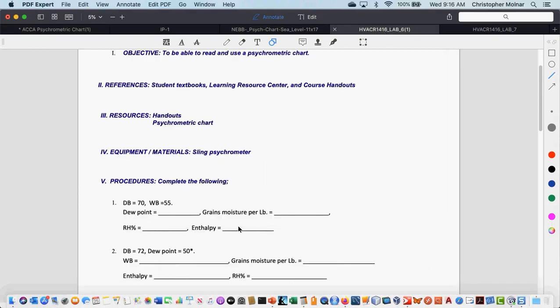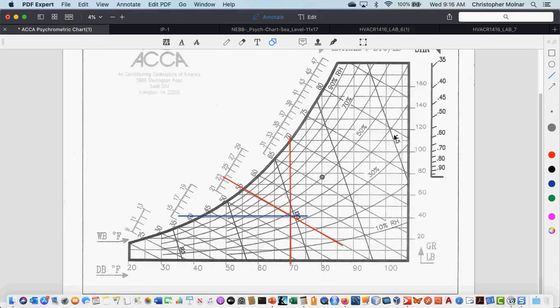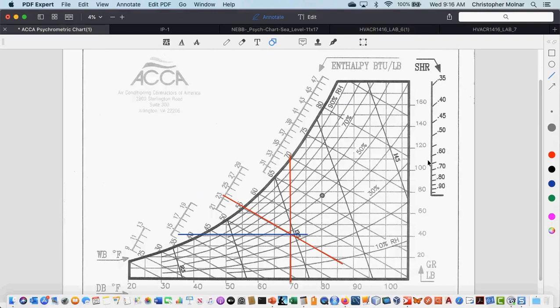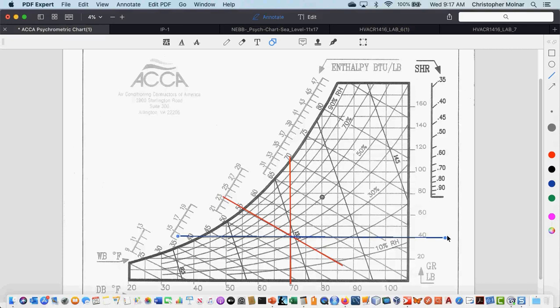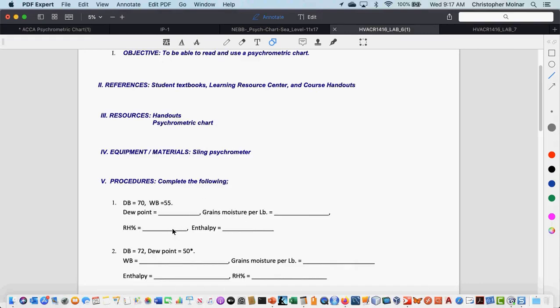Okay, so the next number we were looking for was grains of moisture per pound. That's right over here on the side. So if I extend this line across, how many grains of moisture per pound do I have? 40. Or 42, 43, it doesn't really matter, just be in the correct range. So grains of moisture per pound is right there at 40.